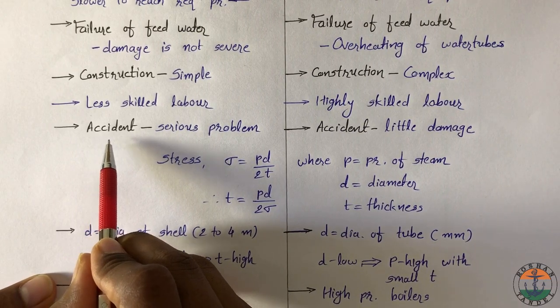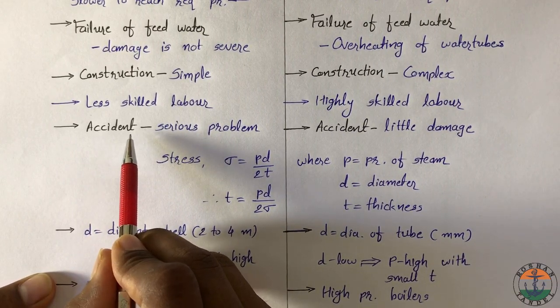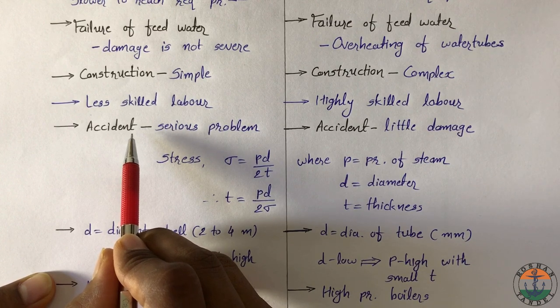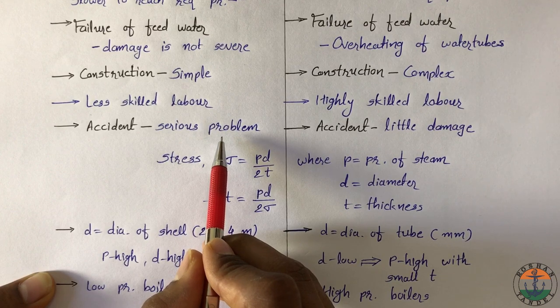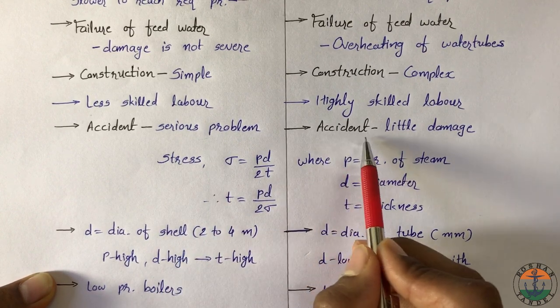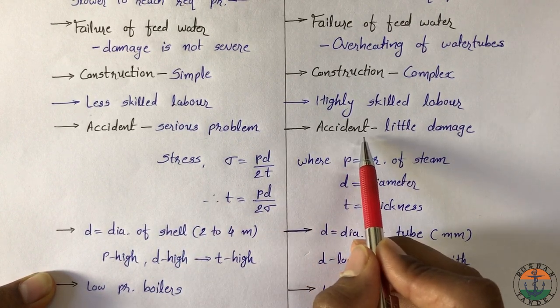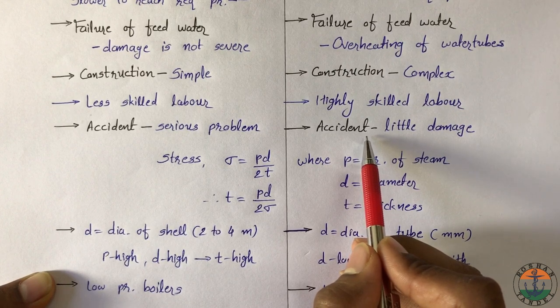In fire tube boiler, whole boiler shell is under pressure. And when the explosion occurs, it becomes very serious problem because of its large water capacity. In water tube boiler, no such explosion occurs even if one of the water tubes fails.